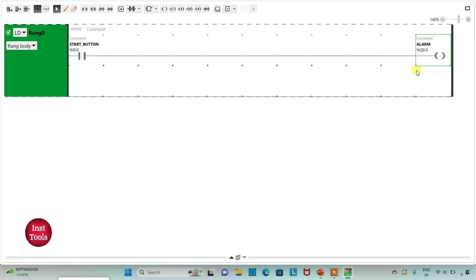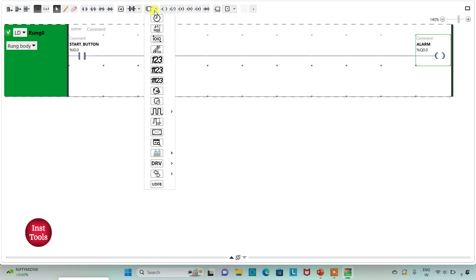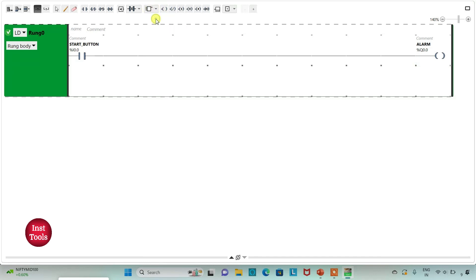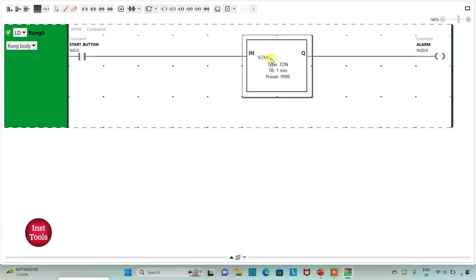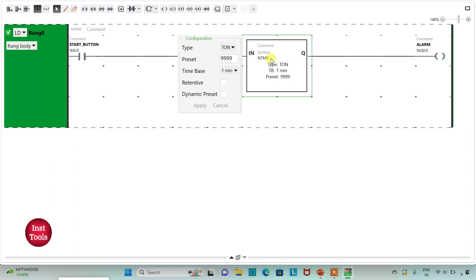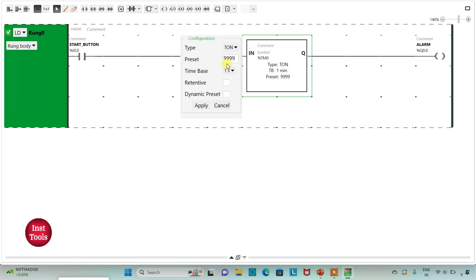After that, the alarm should turn on after 30 seconds. So for that I will use a timer here. That will be TON. I will change time base to one second and preset value as 30. Then I will click on apply.